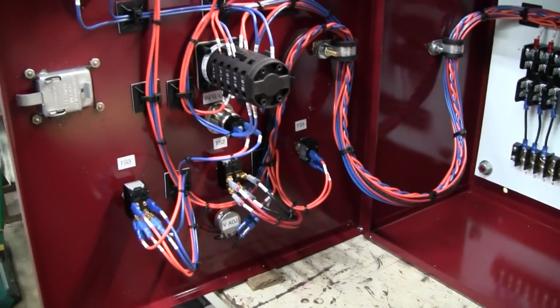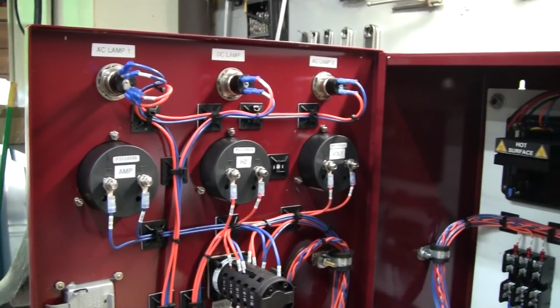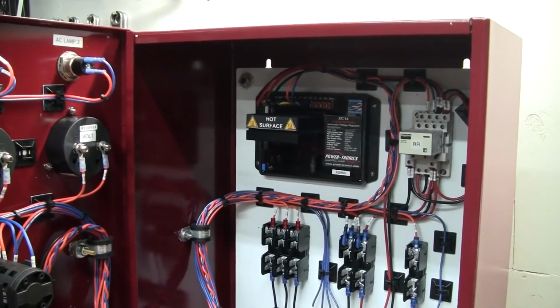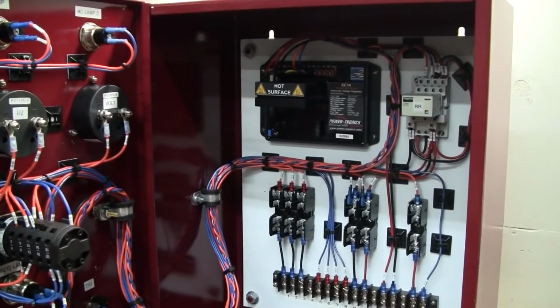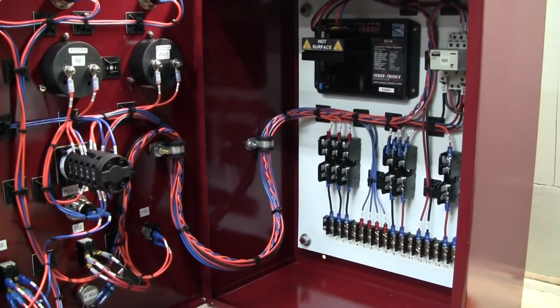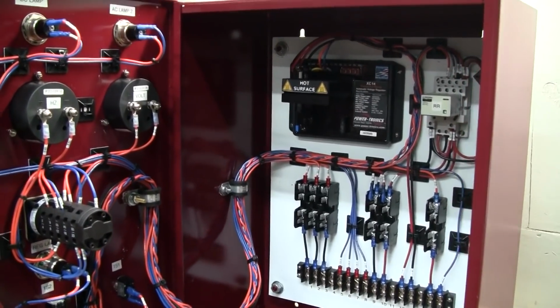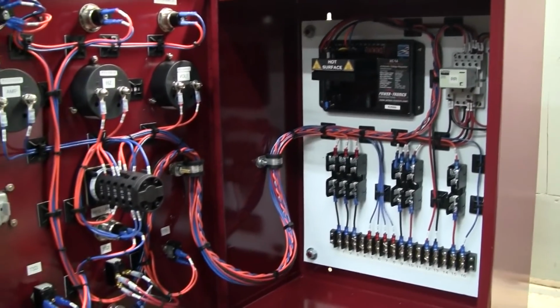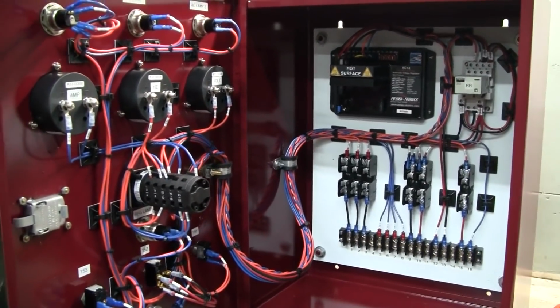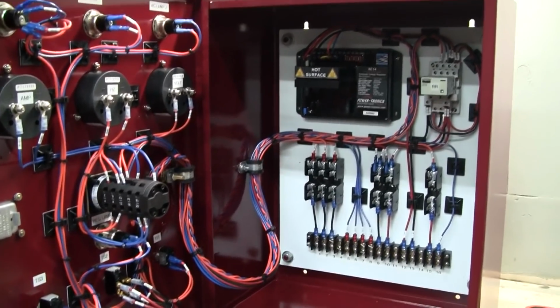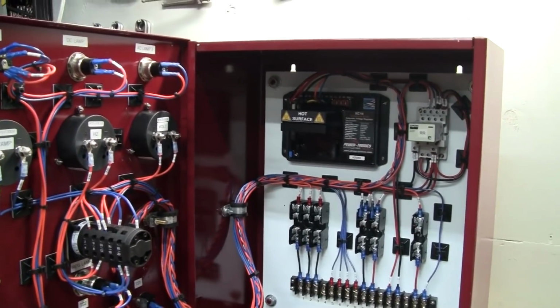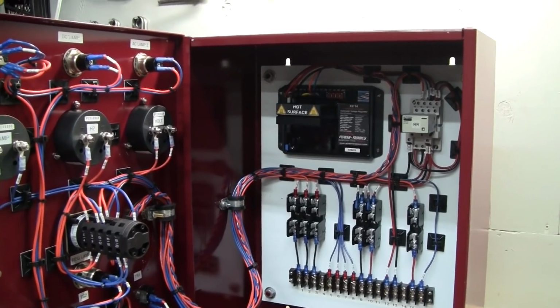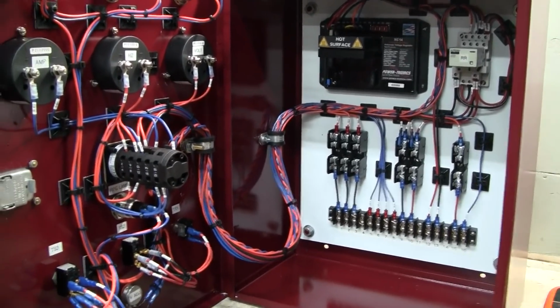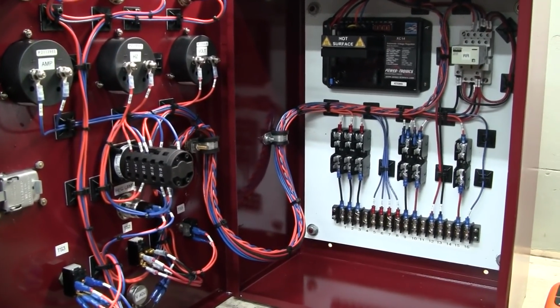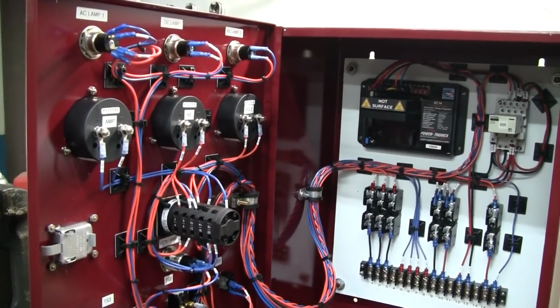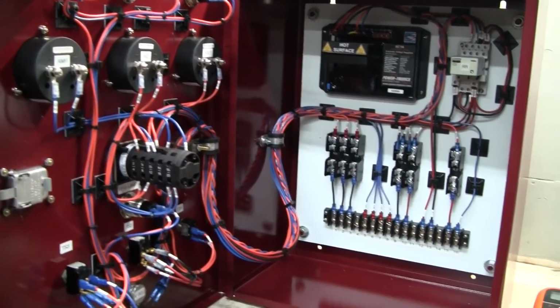So I don't know if I even mentioned that at the beginning of this video. It's a gasoline start, diesel run gen set. So in cold conditions, he will have to start on gasoline and run on gasoline for 5 to 10 minutes before the thing is ready to switch over to diesel, just to get the engine thoroughly warmed up. And at that time, the gen set will be running below operating speed, which is 1200 RPM. 1200 RPM is the rated speed because it's a 6-pole generator.